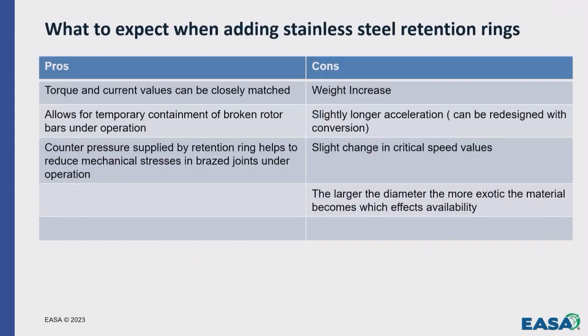So just a few things. When you convert from aluminum to copper, before we get into the intricacies of the stainless steel, there's a couple of questions that always come up. What are the pros and cons? You have an existing motor that's already running in an application. If you go from aluminum to copper, one thing you don't want to do is change performance. So you can't just change from straight aluminum to straight copper, because you change your rotor cage resistance so much it'll change the performance.